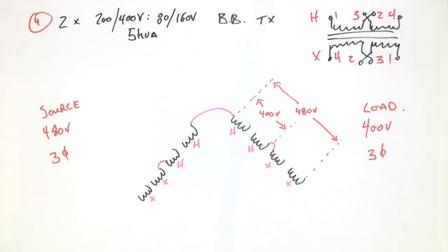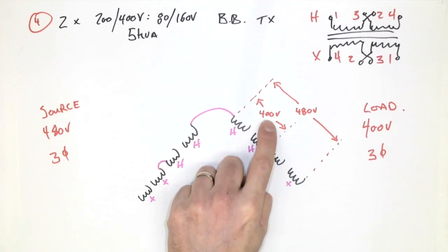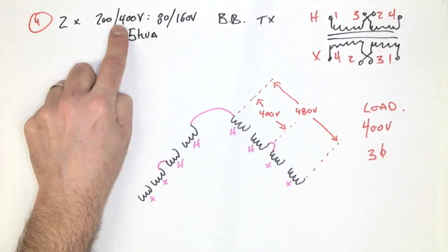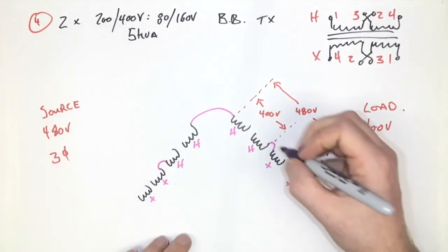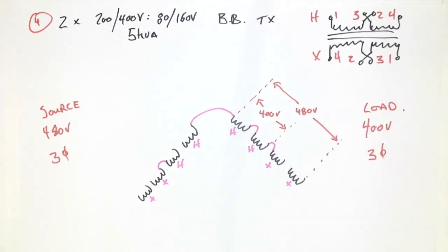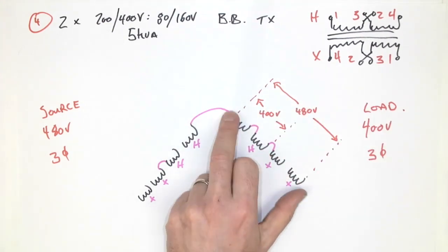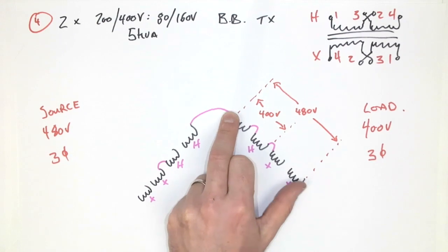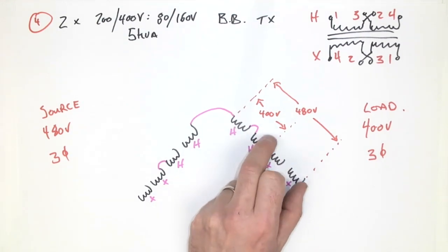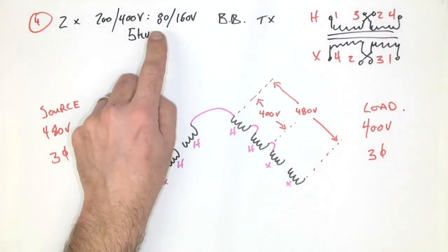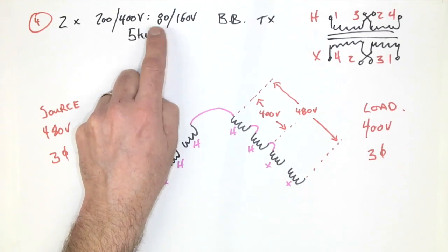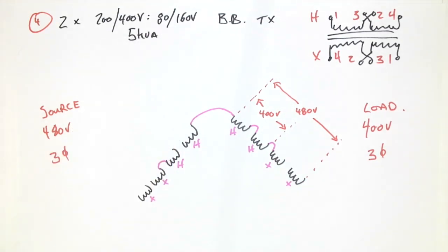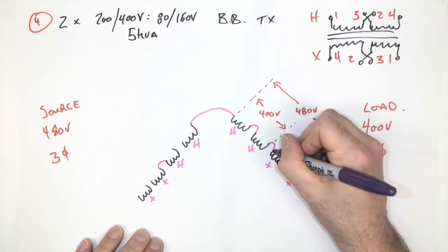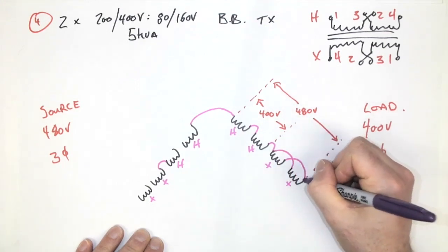Okay, so the X windings and the H windings. How do I get 400 volts here? Well, it looks like I need to connect them in series. So that would be a series connection. Now over here, I need to go from 400 to 480, which means I need 80 volts across these windings, and 80 volts we see identified up here. That would mean they need to be in parallel. Okay, well, parallel means I need to do something like this.